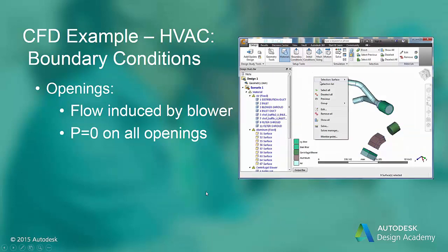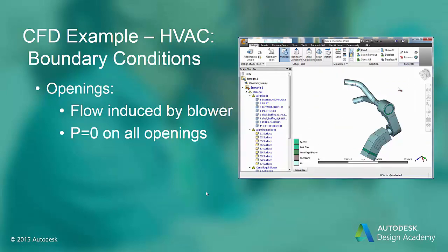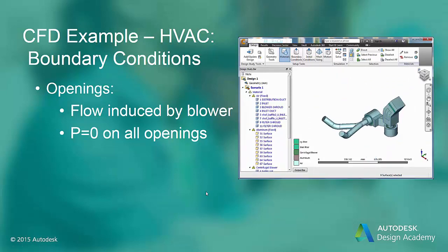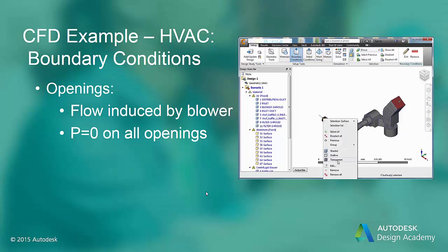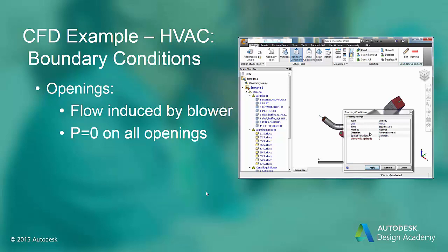For the HVAC duct system, the flow is induced by the centrifugal blower, so we have no inlet boundary conditions to set. All of the openings are exposed to atmospheric conditions, so we set P equals zero on all openings. Based on the internal model pressures, the air will either flow into or out of these openings.